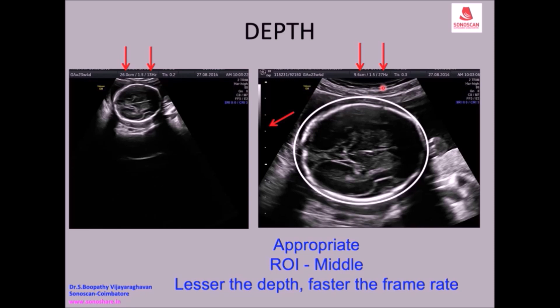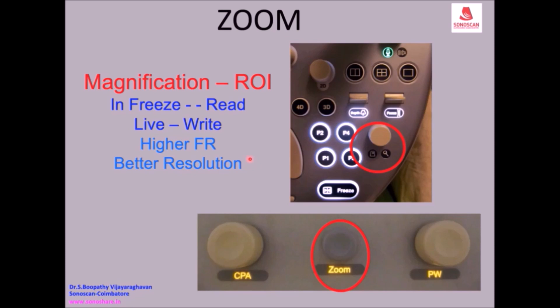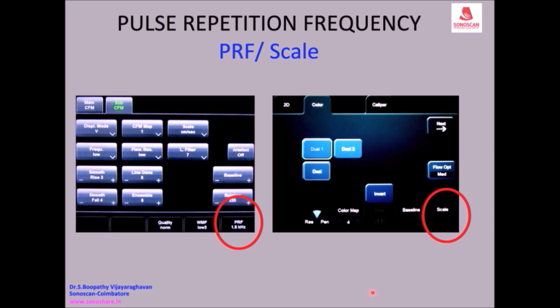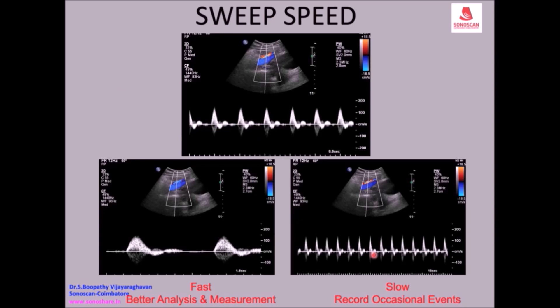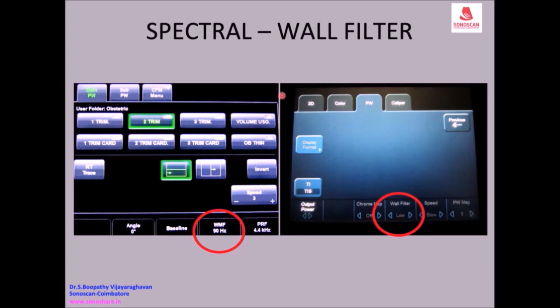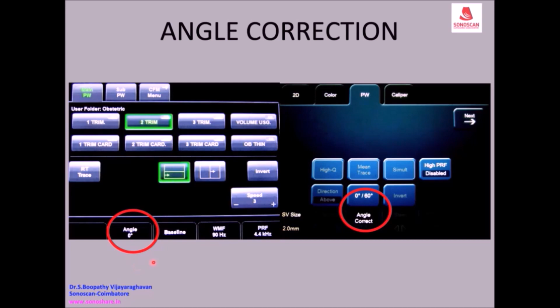When you increase the depth, the frame rate falls to 13, whereas here it is 27, because of the higher frame rate, better resolution. Below this in the panel, by rotating or toggling you can adjust the speed to show more number of cycles. So there is wall filter adjustment in the spectral Doppler. And the knob here below you can use to adjust the angle correction. So this is the angle.